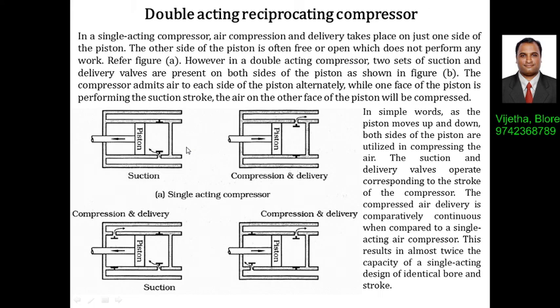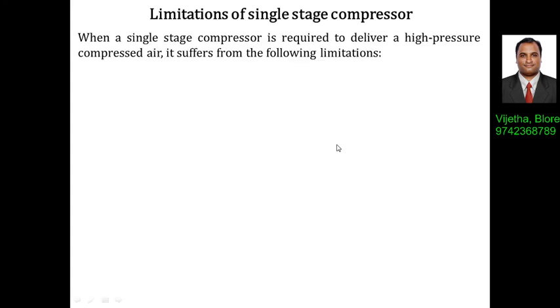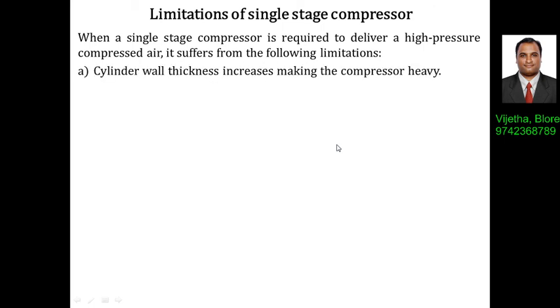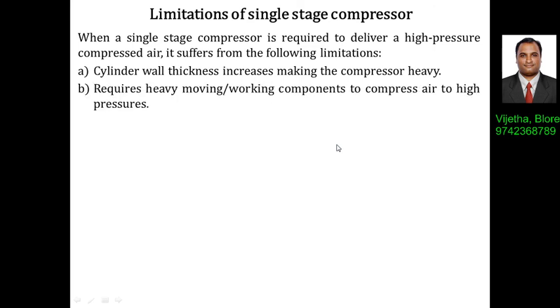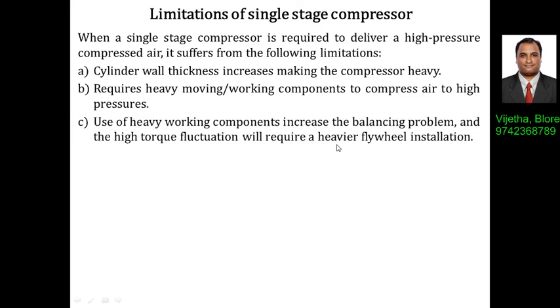Now we discuss the limitations of single stage compressors. When a single stage compressor is required to deliver high pressure compressed air, it suffers from several limitations. Cylinder wall thickness increases, making the compressor heavy. It requires heavy moving and working components to compress air to high pressures. Use of heavy components increases the balancing problem, and high torque fluctuation requires a heavier flywheel installation.